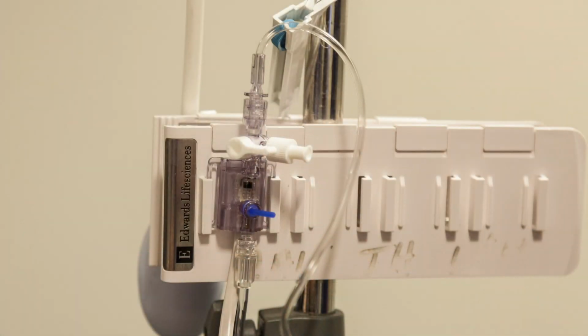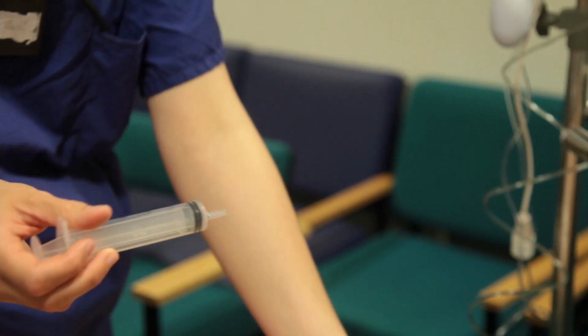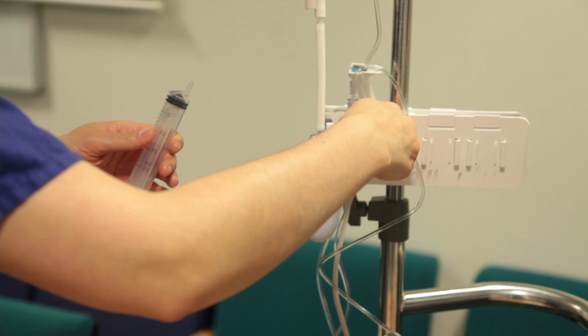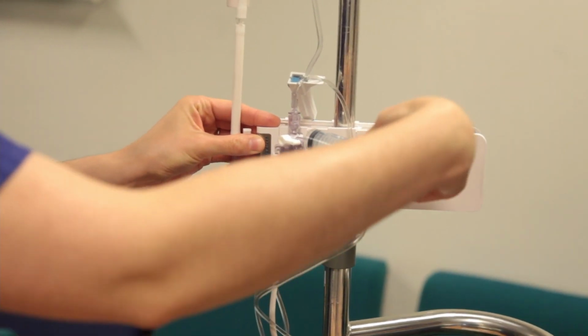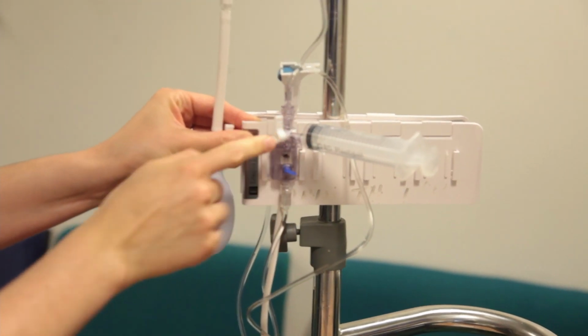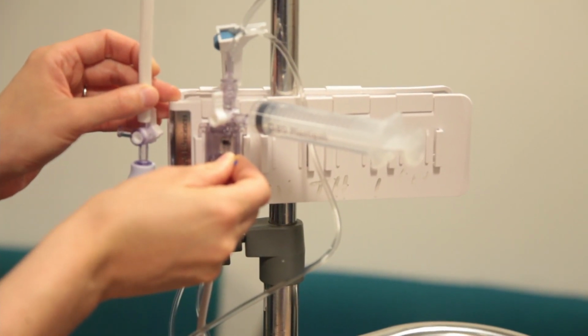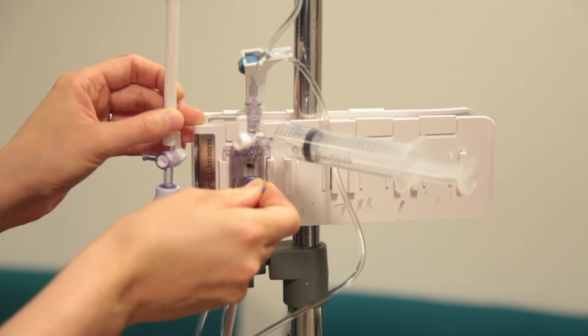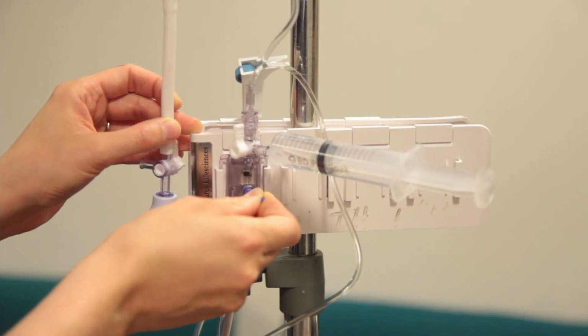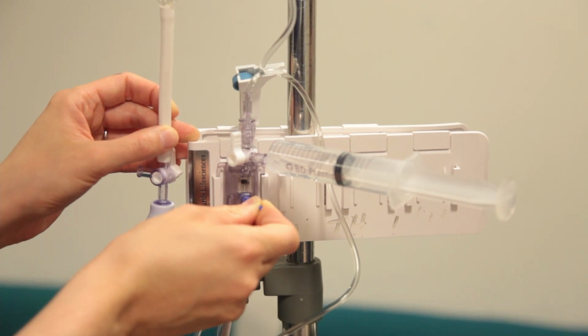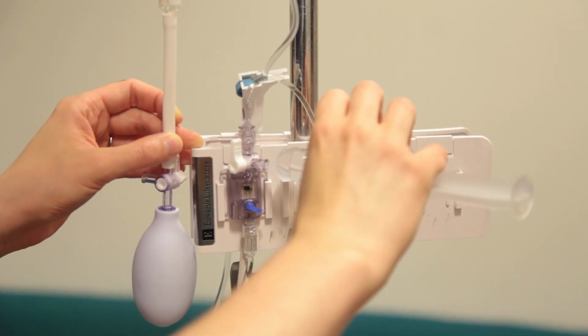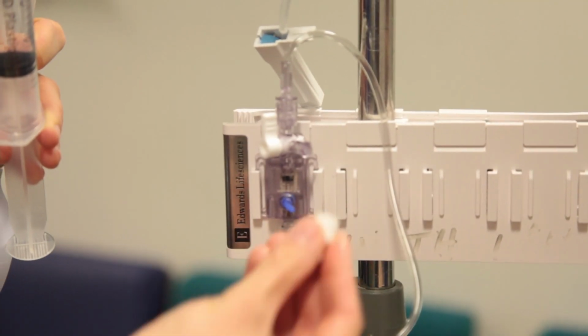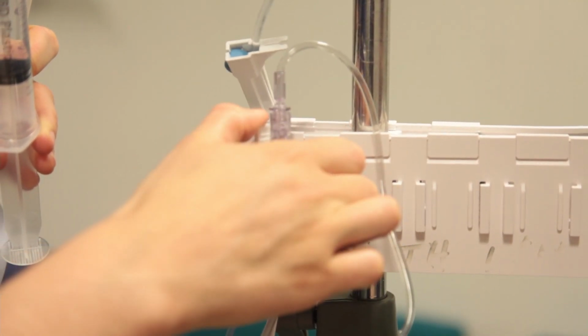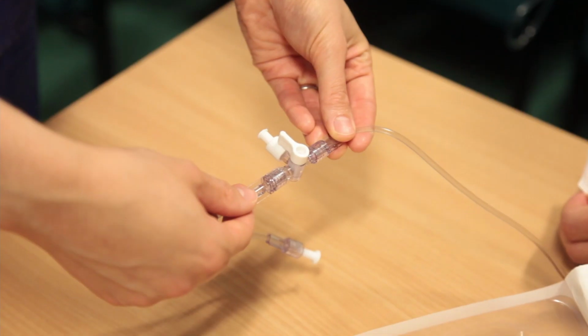Insert the transducer module into the holder itself. Open up a 20 ml syringe and, ensuring that the off arm of the bung is pointed towards the patient end of the circuit, pull the blue rubber band and the syringe should fill with saline. This eliminates any residual air in the bung port. Once this is done, replace the bung and turn the off arm back towards the bung.